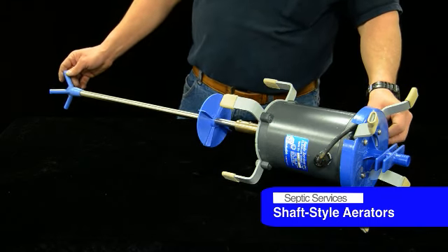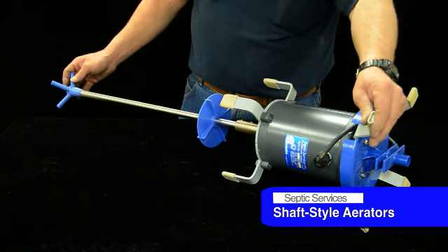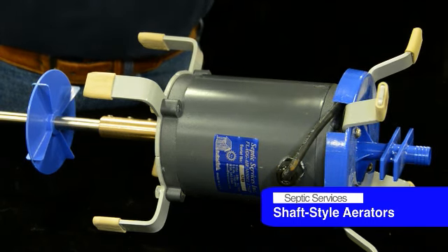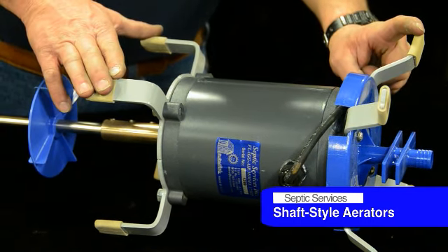Generally speaking, if you get one in for a repair, these rubbers will be worn from vibrating on the concrete and stuff. You want to make sure the brackets are in good shape and replace them if they need to be.